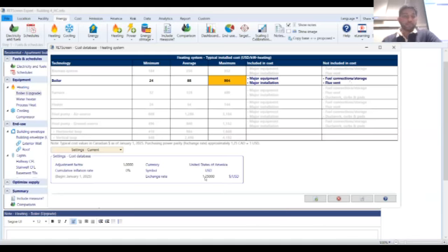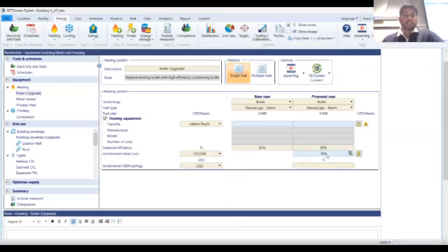but it clearly shows you what's included and what's not. And at the bottom, you can see it also shows the exchange rate that Hardik was talking about. We've changed the units, and these numbers are accounting for the exchange rate between Canada and the US. So I click on paste data and I see 904, but that doesn't seem right, does it? $904 for a condensing boiler. If you see on the left, it says USD per kilowatt. That's $904 per kilowatt of boiler capacity.